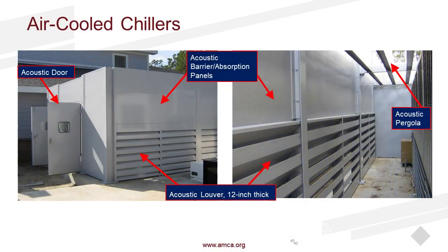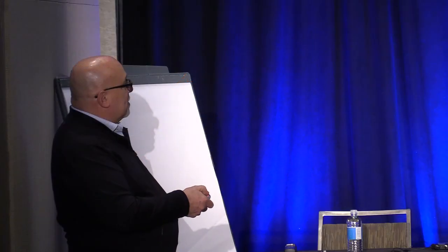Usually, just so you know, this is either 2 or 3 feet above the top of the fans to the bottom of this, so there's clearance if you have to pull a fan. And here's one where you really have to shoehorn it in: you've got a skirt of acoustic louvers, acoustic panels above to control noise, a double door for access to pull the unit out, and then pergolas at the top here.